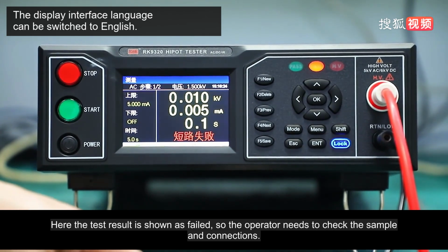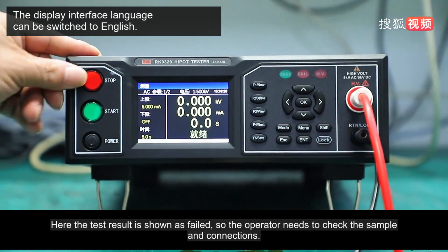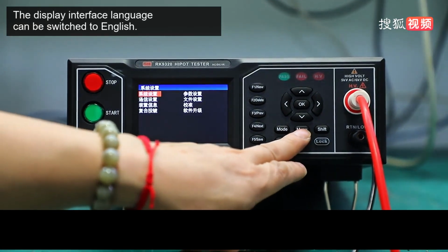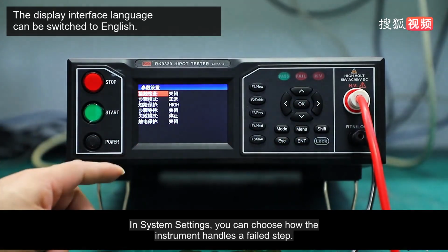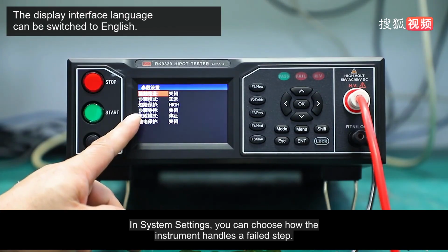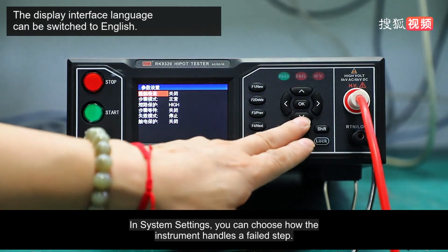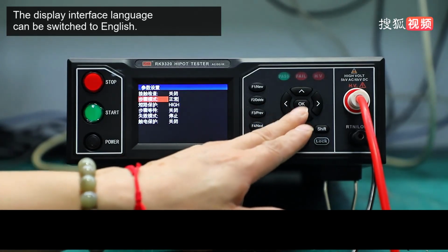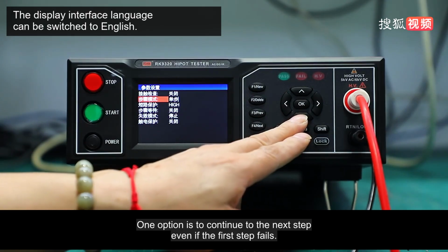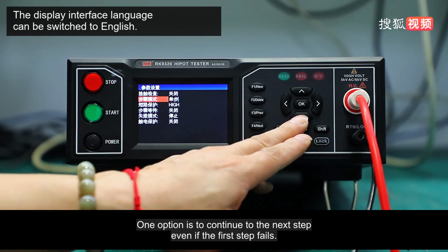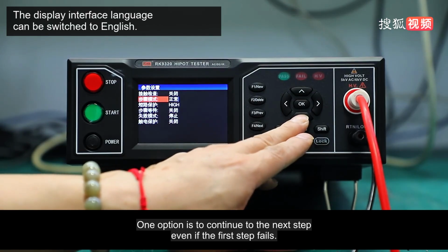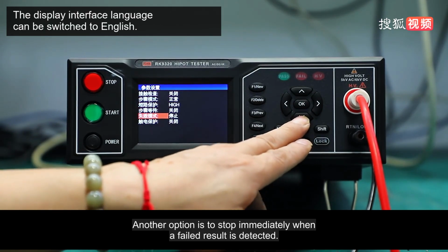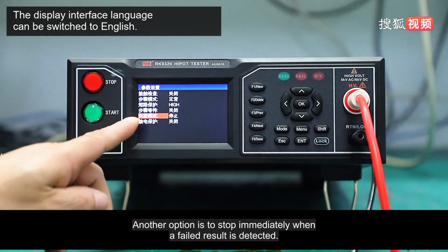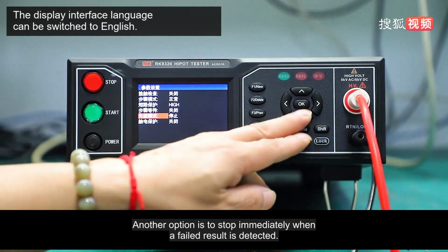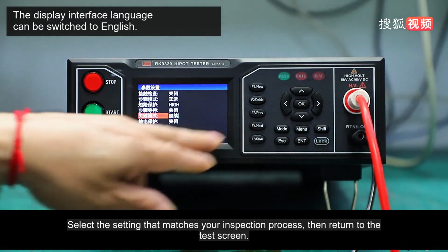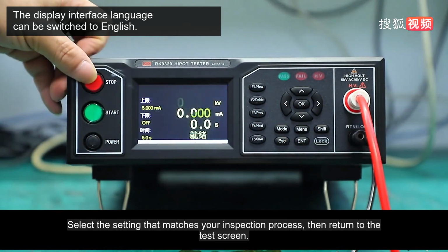Here the test result is shown as failed, so the operator needs to check the sample and connections. In System Settings, you can choose how the instrument handles a failed step. One option is to continue to the next step even if the first step fails. Another option is to stop immediately when a failed result is detected. Select the setting that matches your inspection process, then return to the test screen.